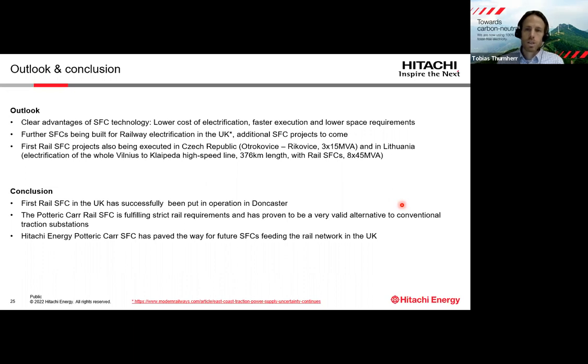So in the Czech Republic, commissioning is being completed on an existing line that has been electrified in Otrokovice, Rikovice, where 3 15 MVA SFCs have been supplied. And then there is another ongoing project in Lithuania, where for the first time a line with a total length of 376 kilometers is electrified with rail SFCs, 50 Hertz. And for that one, 8 times 45 MVA SFCs are supplied.